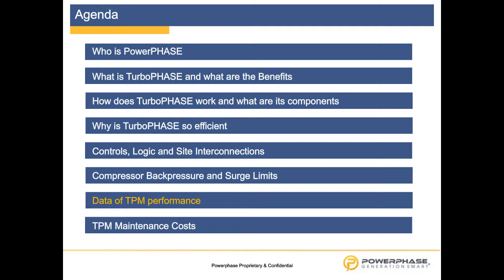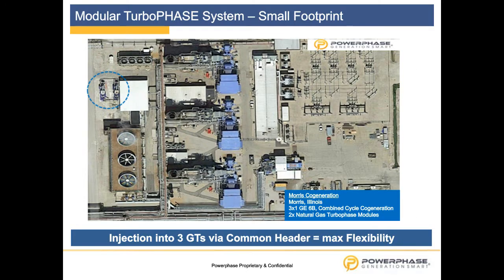I would like to go into two installations right now, on a 6B and on a 7FA. What we have here is a 6B installation in Morris. You see on the left side of this picture, in the framed circle, the 2 TPMs that I showed you at the beginning of this presentation, right next to the chiller building. These 2 TPMs are connected on a common header, utilizing existing piping racks, into the 3 6B gas turbines here in the middle, allowing the customer maximum flexibility in operational cycles and in plant maintenance.